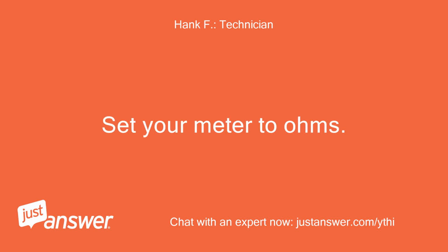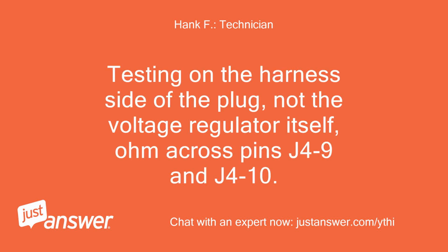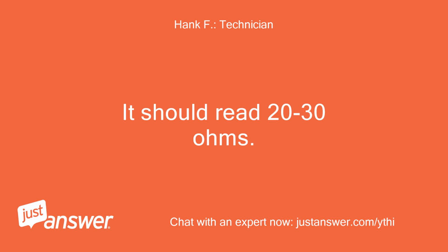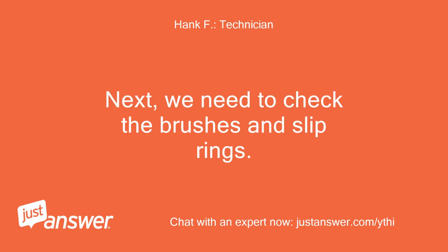Set your meter to ohms. Testing on the harness side of the plug, not the voltage regulator itself, ohm across pins J4-9 and J4-10. It should read 20 to 30 ohms. Next, we need to check the brushes and slip rings.